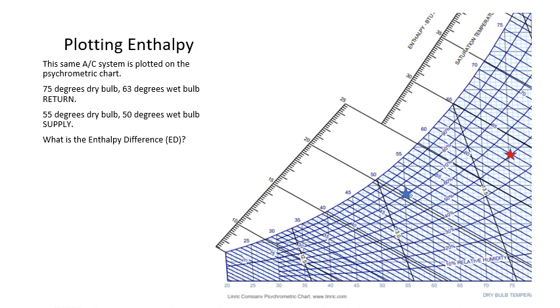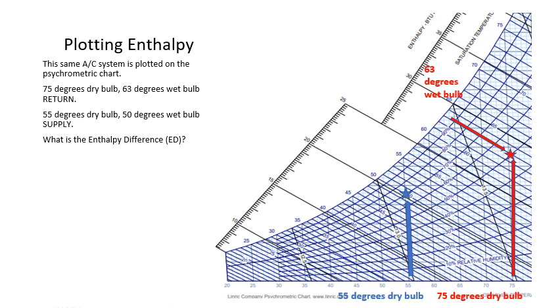We still have our sample air conditioning problem that we're working through. In this system, as we can see here, we have plotted two operating points — our return and our supply. Our return was 75 dry bulb, 63 wet bulb. Our supply was 55 dry bulb and 50 wet bulb. That's how we arrive at our operating points.